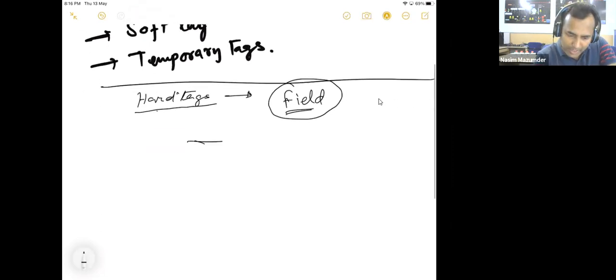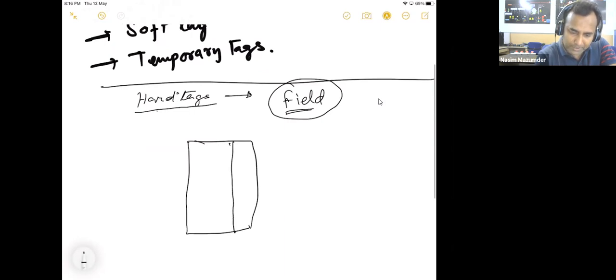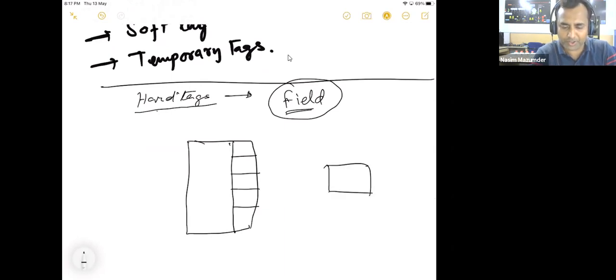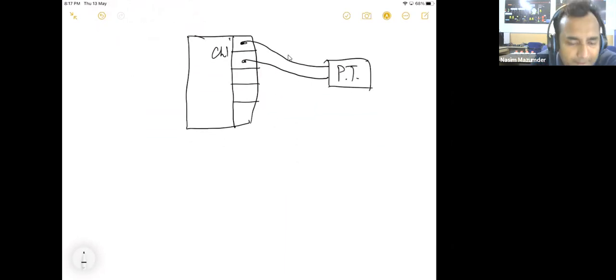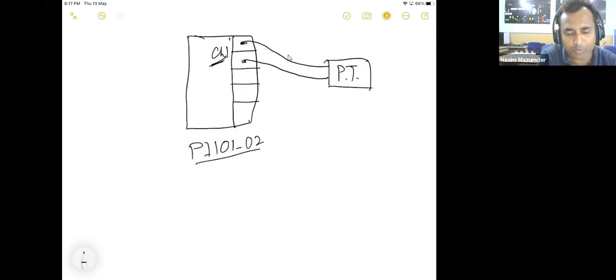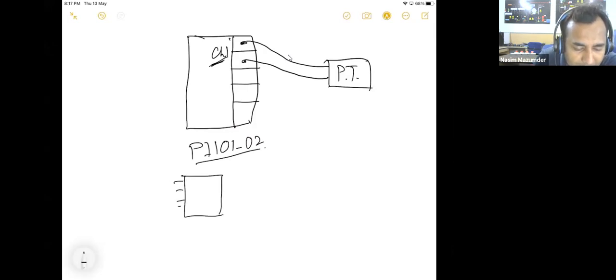Okay. Suppose I am having a card here. Suppose this is an input card and suppose I am having a pressure transmitter over here. This pressure transmitter, say, is connected with this particular channel. Say this is channel number 1. Now, in my software, I have to assign this particular channel. Just now I showed you that I was writing something like PI 101 underscore 02 or so. This is a tag name. And where did I assign it? Assigned to some pin in my software.